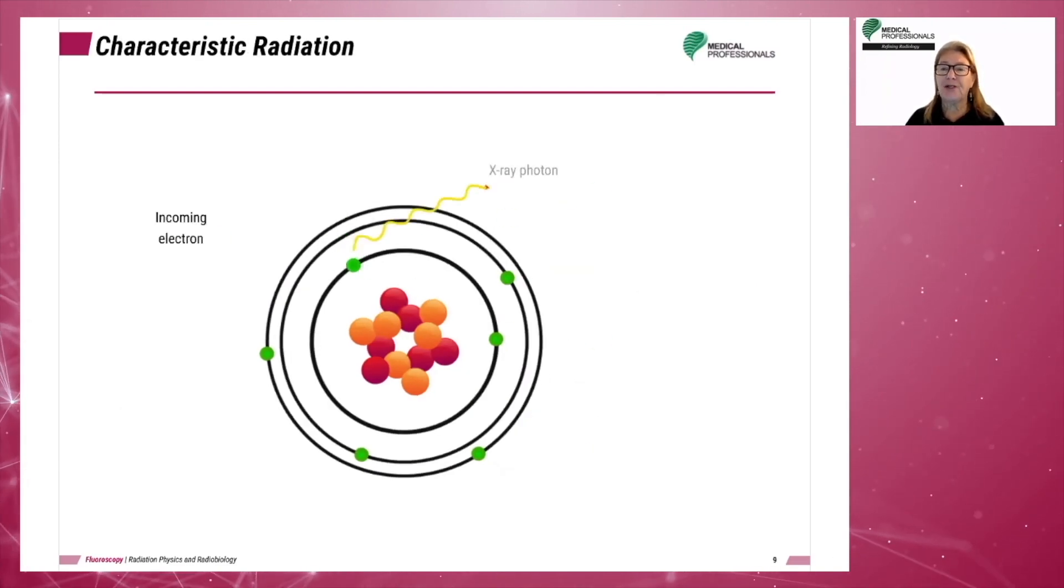Characteristic radiation is produced when the incoming electron is of sufficient energy to dislodge an electron from the K shell of the tungsten atom. The energy of the incoming electron must be at least 69.5 kilovoltage peak. We will round that up to say 70. Settings on an X-ray unit less than 70 kVp produce no characteristic radiation.